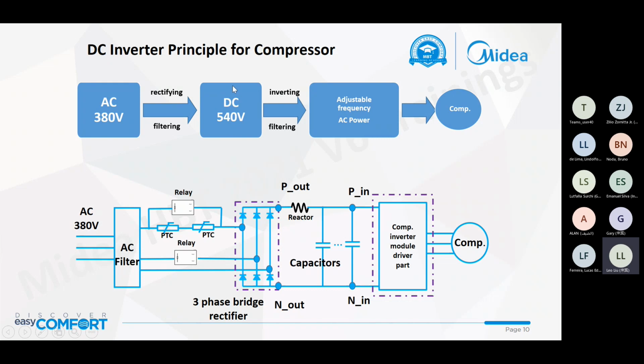So that's why we call it DC inverter technology, because we got the DC voltage to the compressor drive board. So below we can see three-phase AC voltage to AC filter, three-phase bridge rectify, capacitors. We got the DC voltage to compressor drive board. So it's not difficult to understand. I think this is a general principle. Not only Midea, but also Daikin, Mitsubishi, LG, they also call it DC inverter technology.